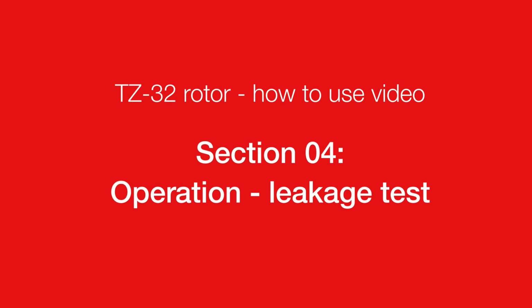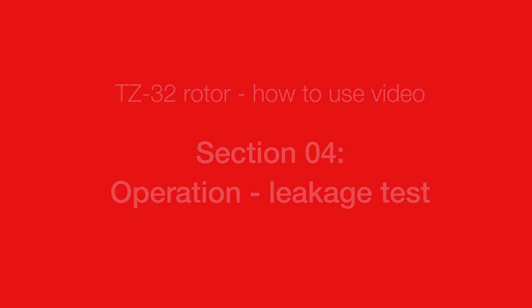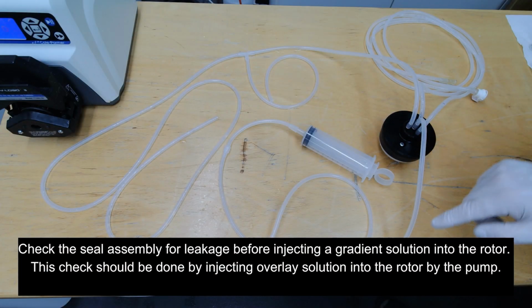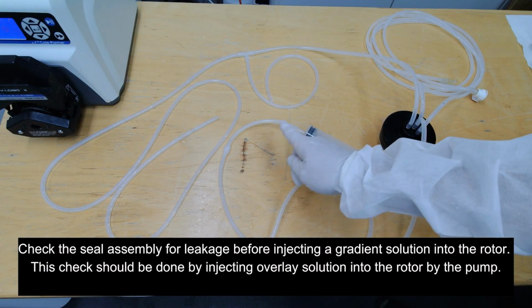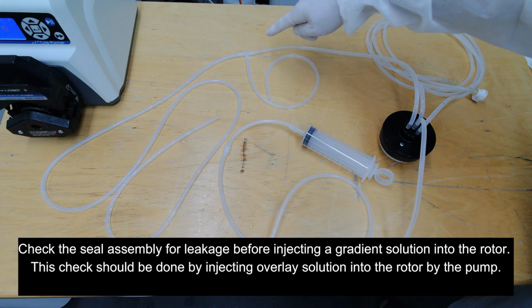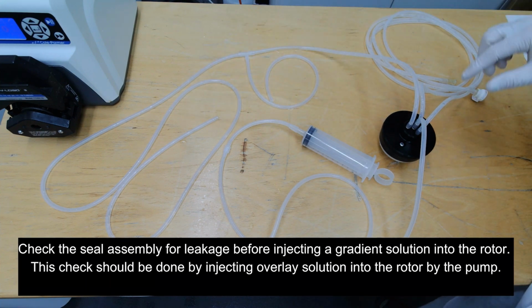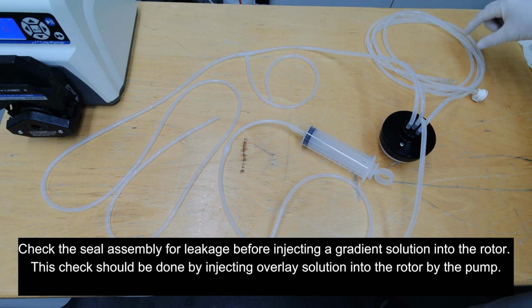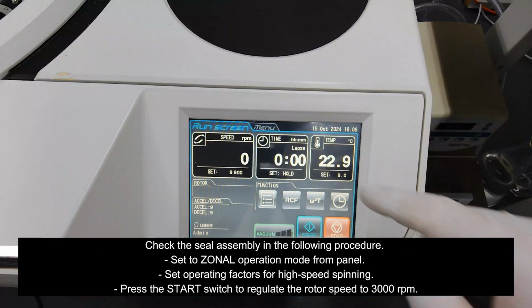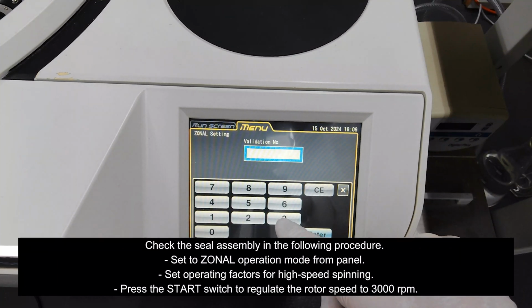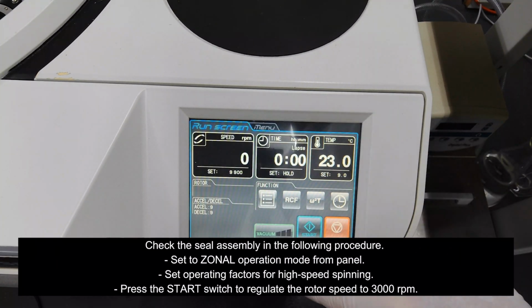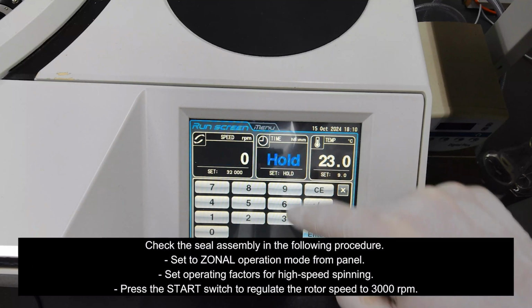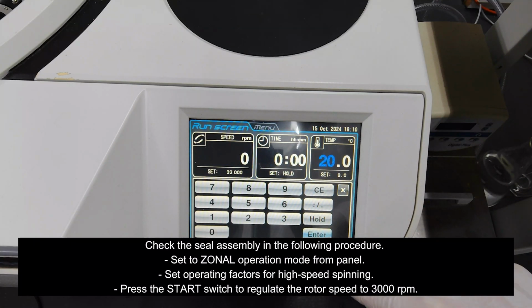How to use video. Section 4. Operation. Leakage test. Check the seal assembly for leakage before injecting a gradient solution into the rotor. This check should be done by injecting overlay solution into the rotor by the pump. Check the seal assembly in the following procedure. Set to zonal operation mode from panel.